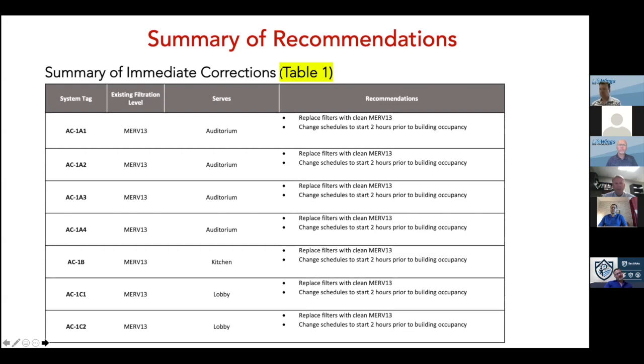You really can take these and start replacing filters with clean filters. And we note if the filters are dirty. Changing schedules to start 2 hours prior to building occupancy. We found a lot of buildings that essentially are off during unoccupied periods, and they don't start till people actually show up. But one of the things that we've been doing is trying to purge, essentially, if units have been off for 8 to 10 hours, by running those ahead of time to clean out the air in the classrooms before students and teachers get there. So we've been doing that a lot.